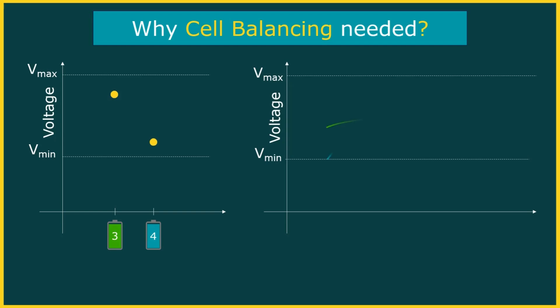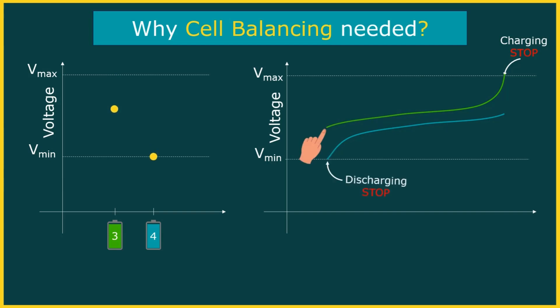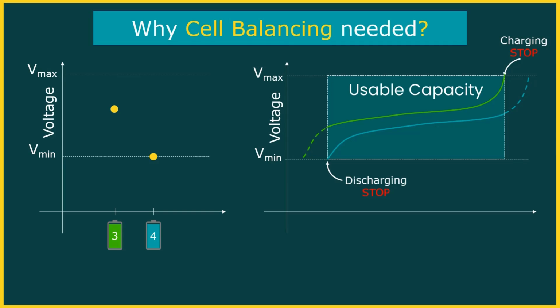During charging, cell 3 reaches its maximum voltage limit, Vmax, before cell 4 is full. The BMS stops charging to protect cell 3, leaving cell 4 undercharged. During discharge, cell 4 reaches its minimum voltage limit, Vmin, before cell 3 is empty. The BMS stops discharging early, leaving cell 3 with unused energy. Repeatedly operating cells at Vmax or Vmin not only wastes capacity but also accelerates cell degradation.